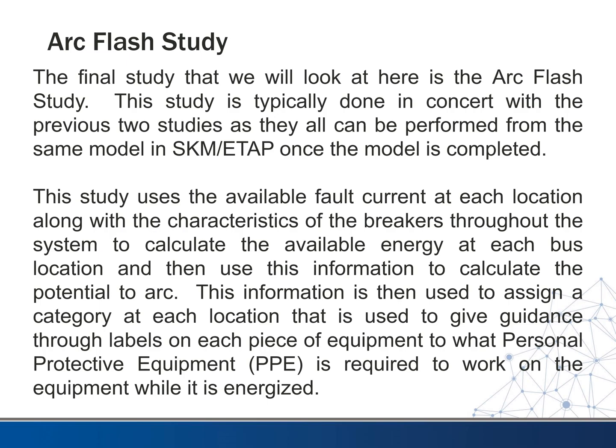We use this information to calculate the potential to arc. There is always a chance that when you're working on energized equipment with tools, you could cause something to arc over — even without directly touching it, you could get close enough for it to arc over to you. Once we make this calculation, the information is used to assign a category defined in NFPA 70E, which is the electrical safety code, at each location.